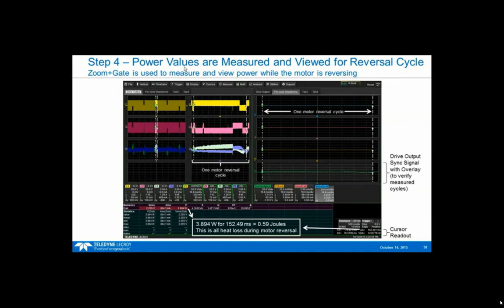He also wanted to measure the power values for a reversal cycle. Now we're looking at this area right here, where there's only one reversal cycle. We picked it up right here through this slight oscillation in the waveform. These are what the waveforms look like during the reversal, and that's the power value. Basically the power during the reversal cycle, or the energy, is all heat loss, all wasted. Now they know what the power consumption and heat loss is for one operating cycle and one reversal cycle, and that happens once a second essentially, so they could calculate the energy over time. Pretty clever.